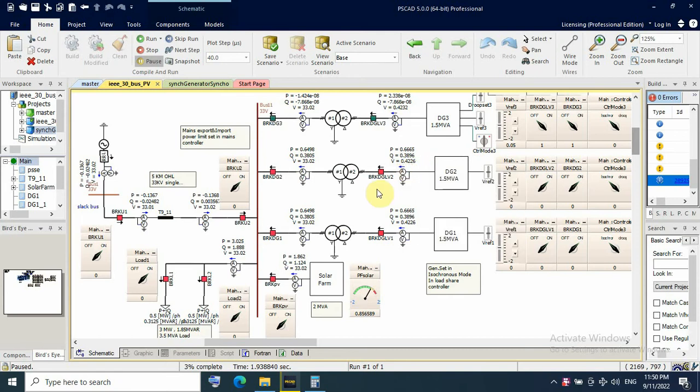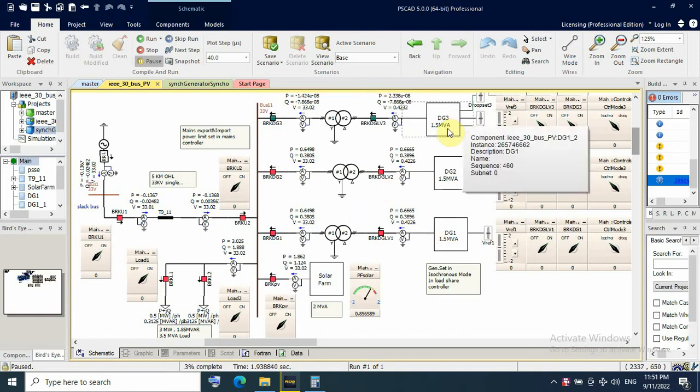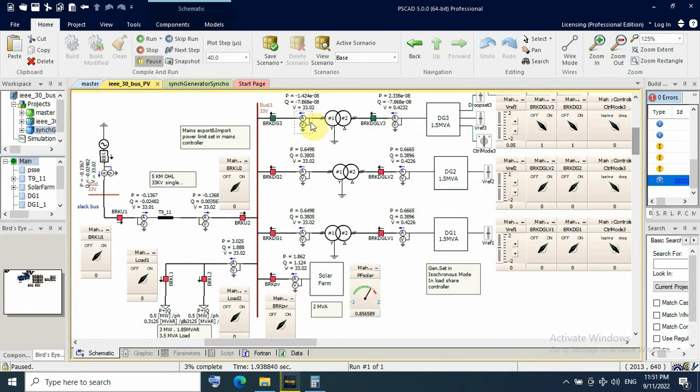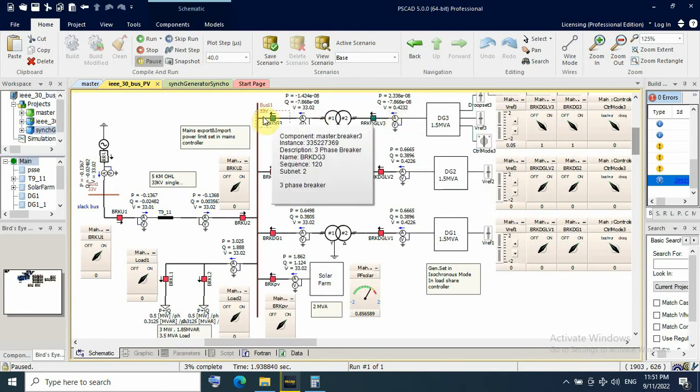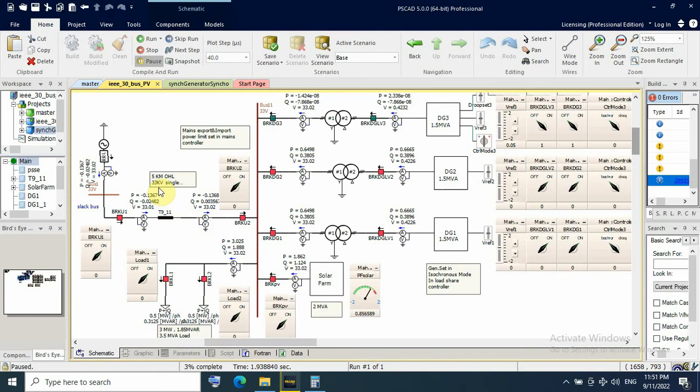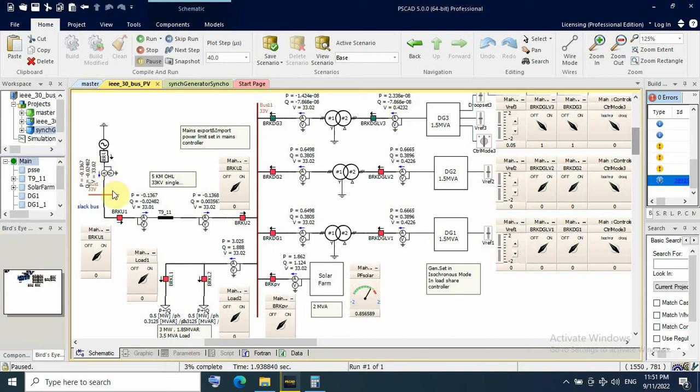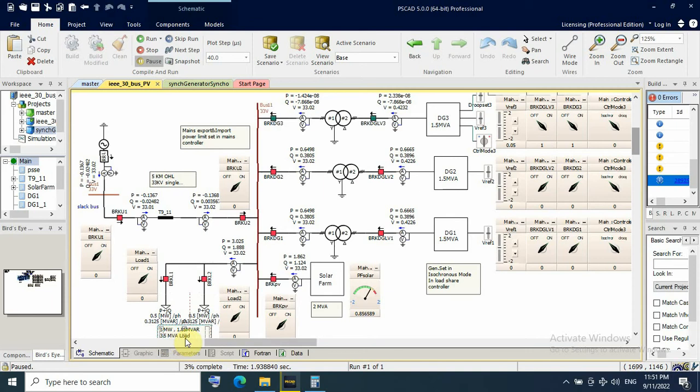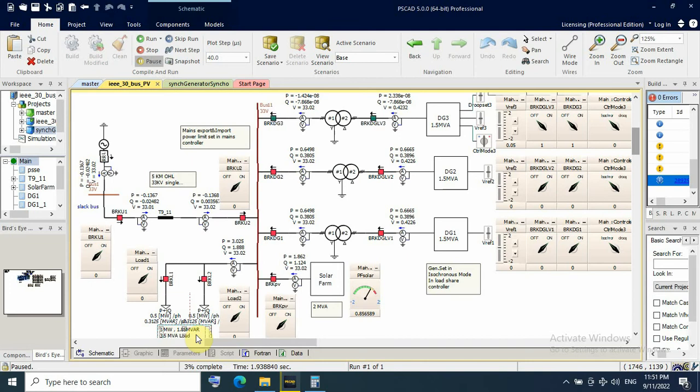First let me show the configuration or single line diagram. We have here three gensets rated 1.5 MVA with a step transformer from low voltage 400 to 33 kilovolts, and then we have grid or utility feeder coming behind single circuit for five kilometers from substation as a slack or swing bus. I have local load rated to 3.5 MVA, 3 MW and 1.85 MVAr in term of active and reactive power, and here I have solar farm rated to 2 MW or 2 MVA.